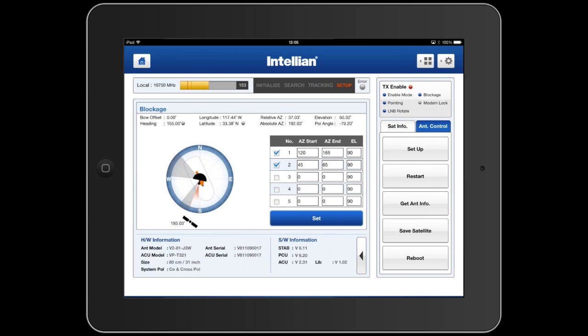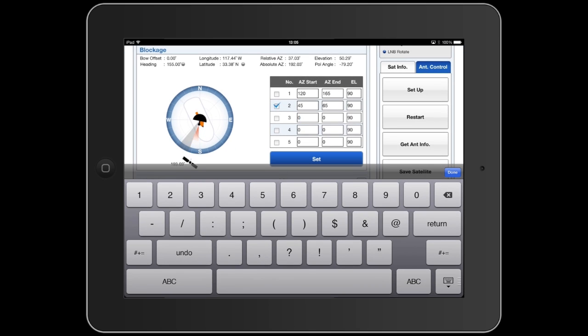The first menu option allows us to select a blockage zone. We can select multiple zones, adjust them in range and azimuth as well as elevation. It's very easy to select the zone or go in and edit it in detail, adding a new zone and then selecting it using the check mark. Once it is set, the graphic will indicate the areas of blockage.